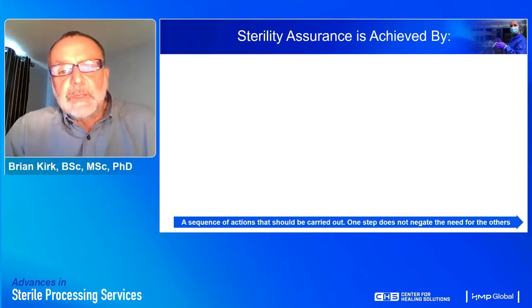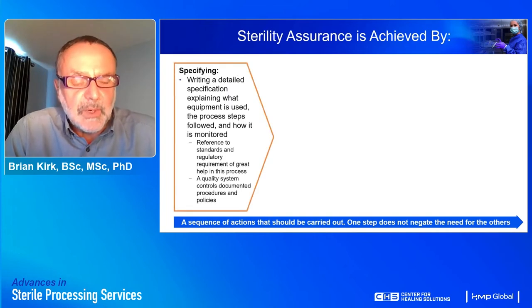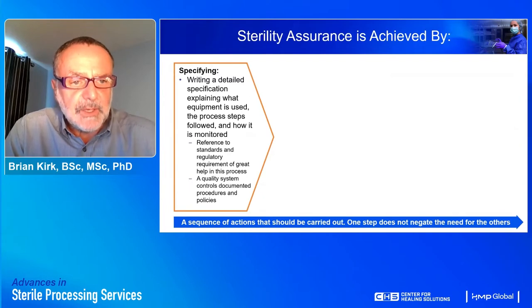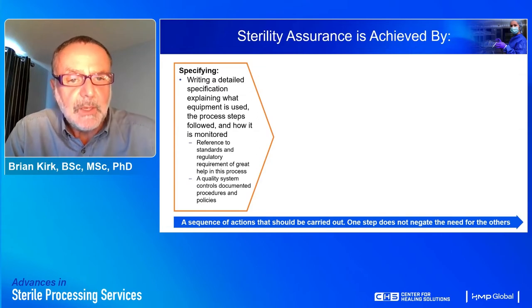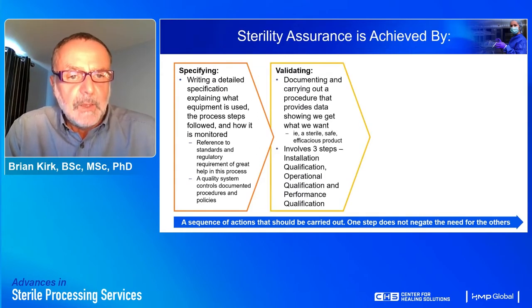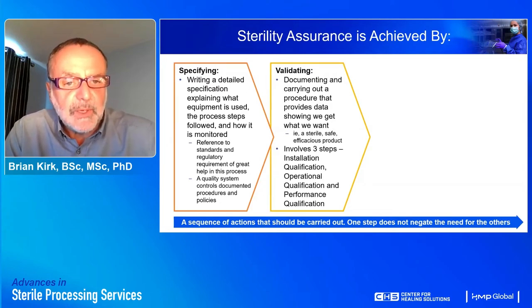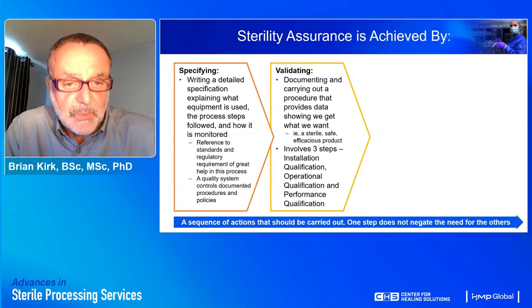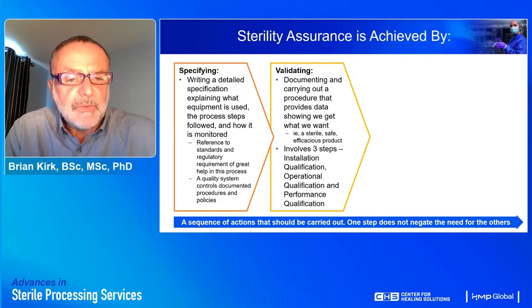Sterility assurance is ensured following three processes. The first is specifying — writing a detailed specification explaining what equipment will be used, the process steps, and how it should be monitored. The second is validation — documenting a procedure that provides data showing what we want is what we get, that is a sterile, safe, efficacious product. Validation involves three steps: installation, operational, and performance qualification.